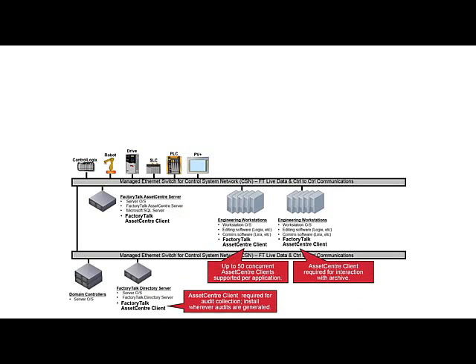The next component is the FactoryTalk Asset Center client. The client should be located on any host that needs access to the FactoryTalk Asset Center archive, as well as any host that will be used for general Asset Center configuration. Also note that the client is the component that collects FactoryTalk audits, meaning it is required on any host from which audits are desired, such as FactoryTalk ViewSE clients, which are not covered in this example. The maximum number of concurrent clients — meaning clients open at any given time — is 50.